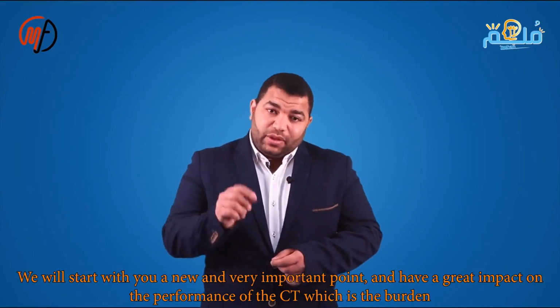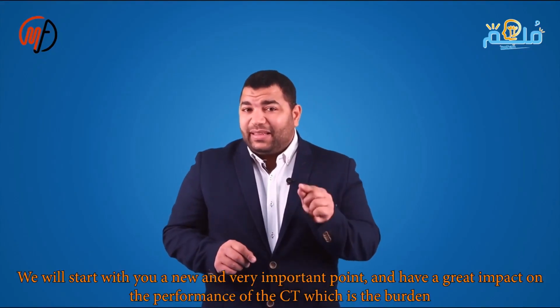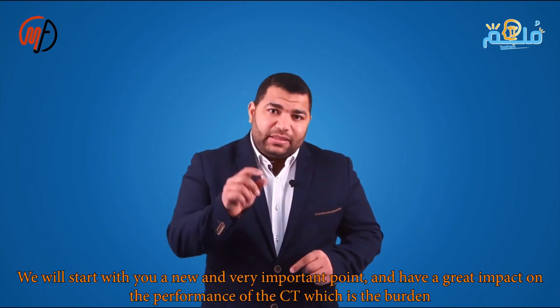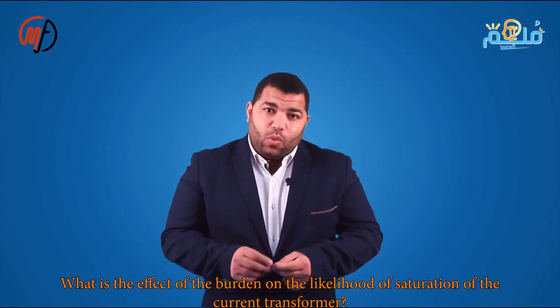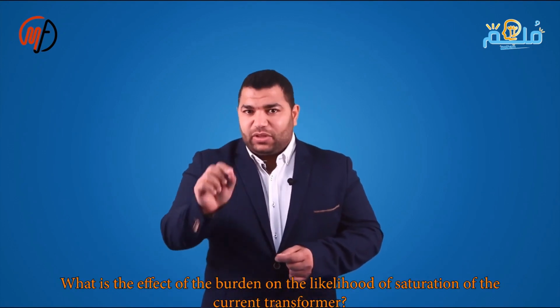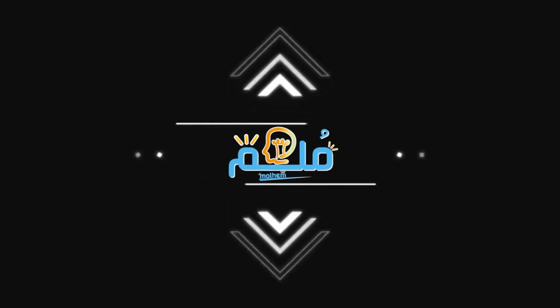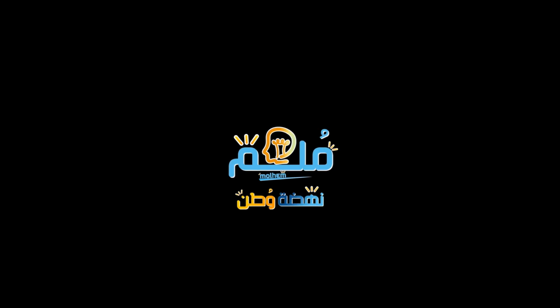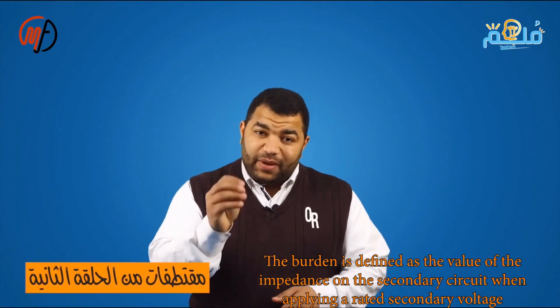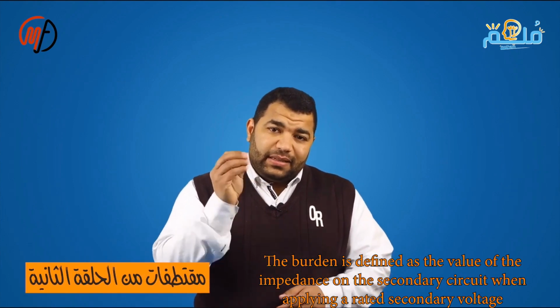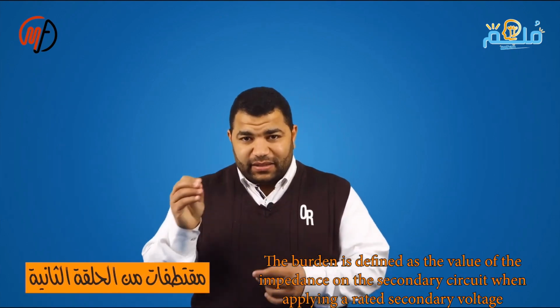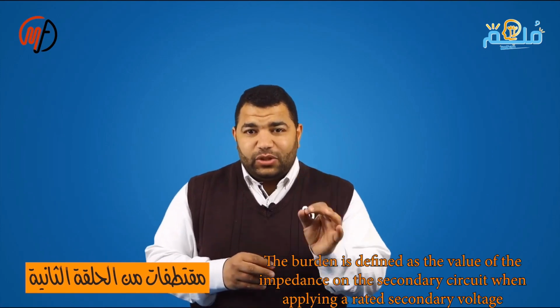Let's start with a new and very important point that has a significant impact on the performance of CT, which is the burden. So what is the effect of burden on the likelihood of a CT becoming saturated? Do you remember what burden is? Burden or load is defined as the value of the resistance present in the secondary circuit when applying the rated secondary voltage.